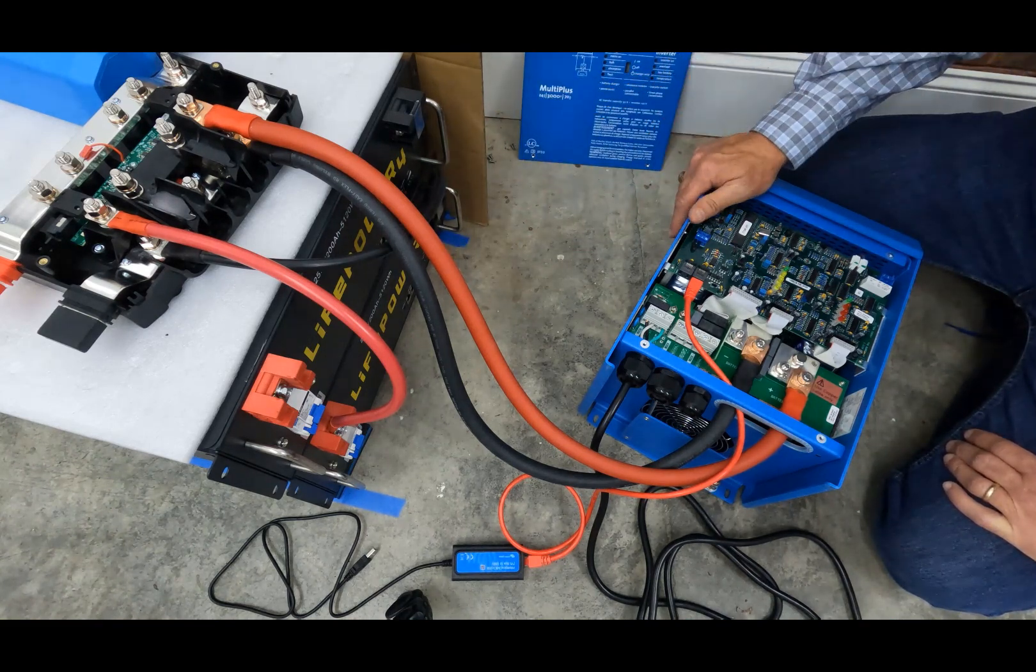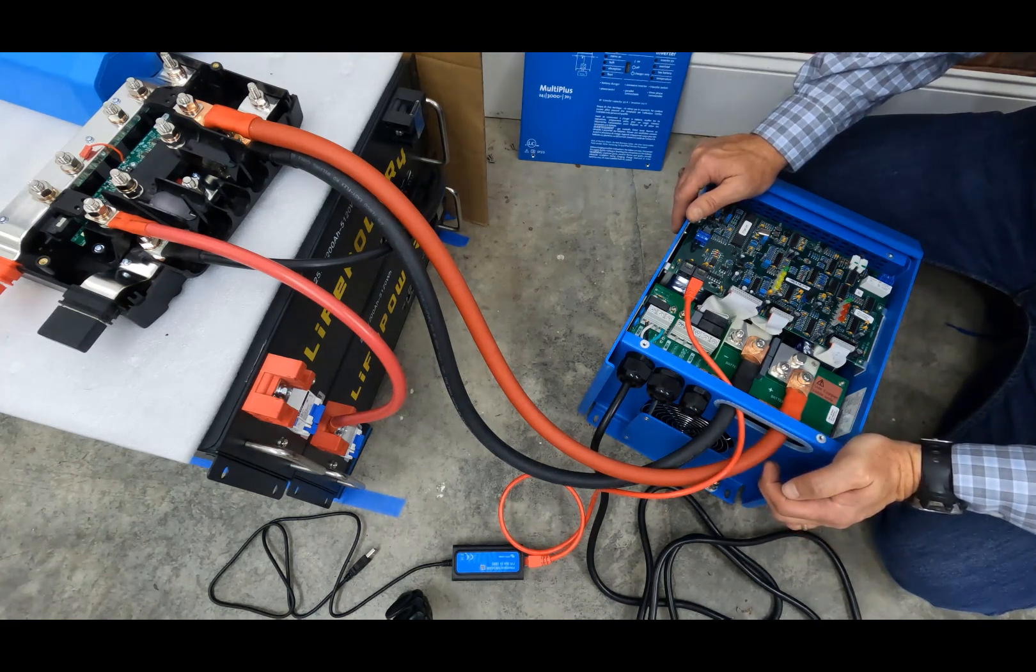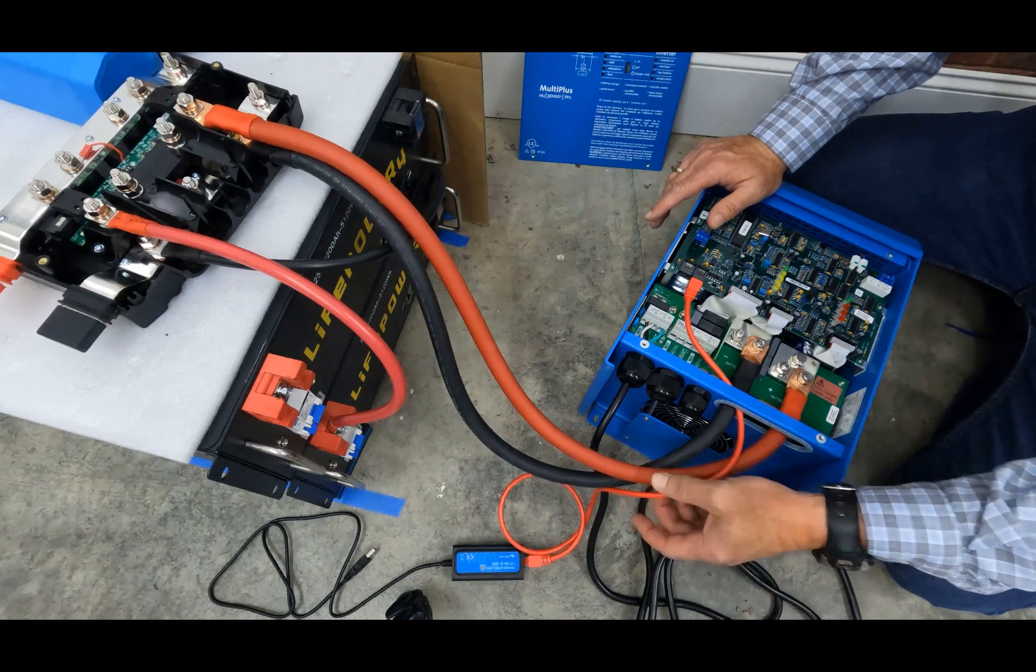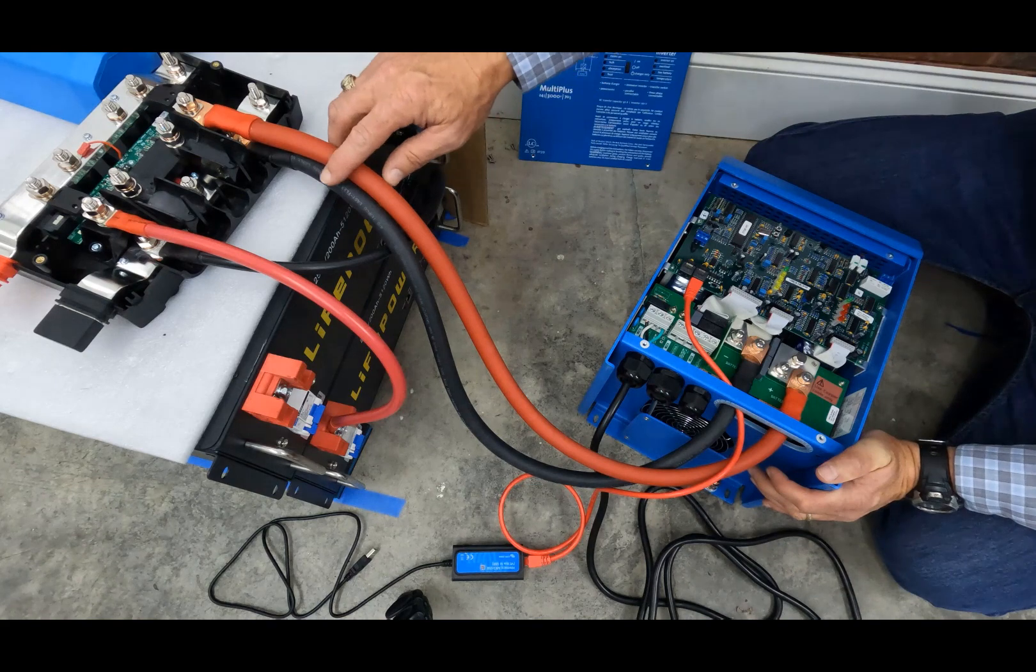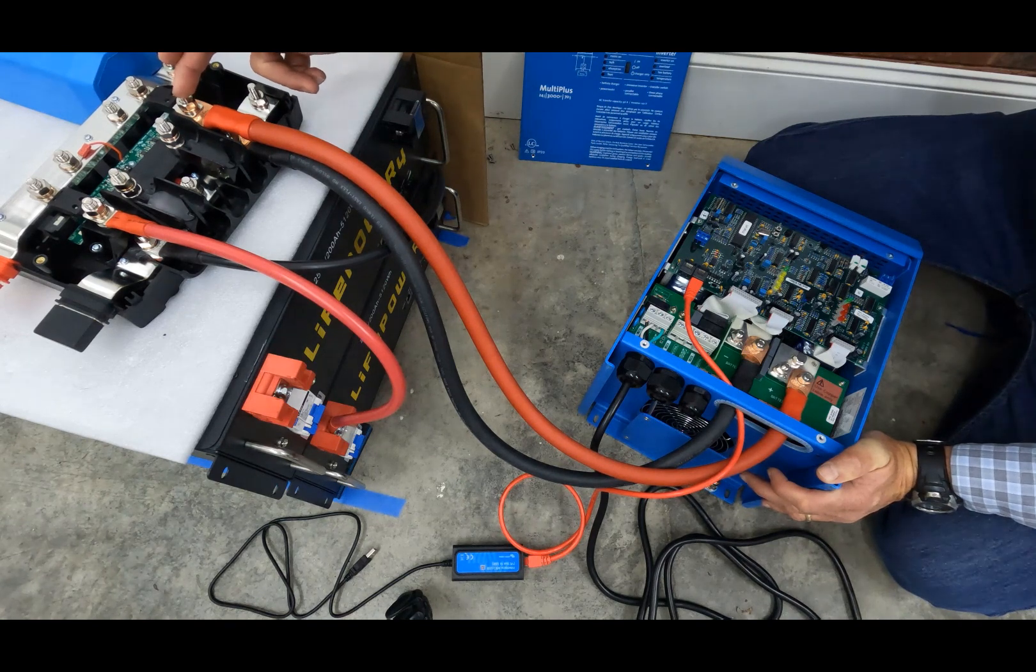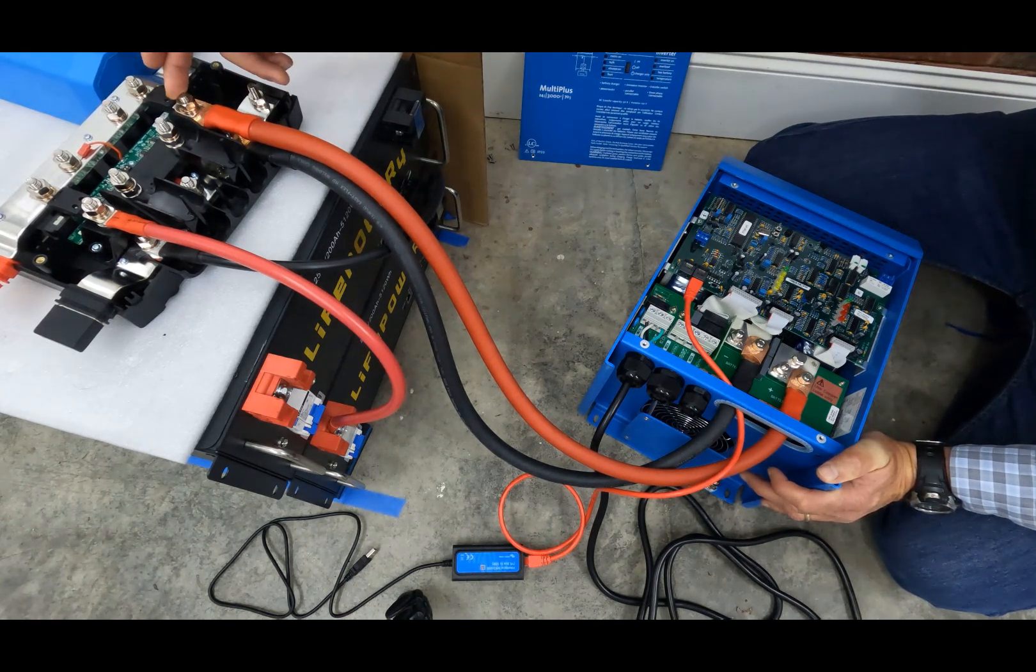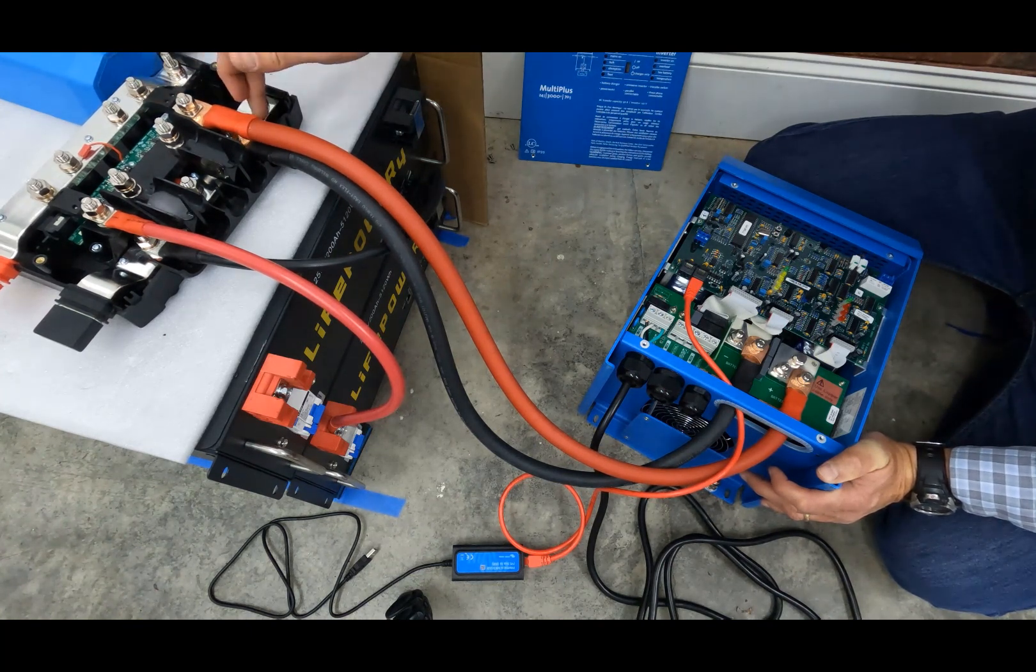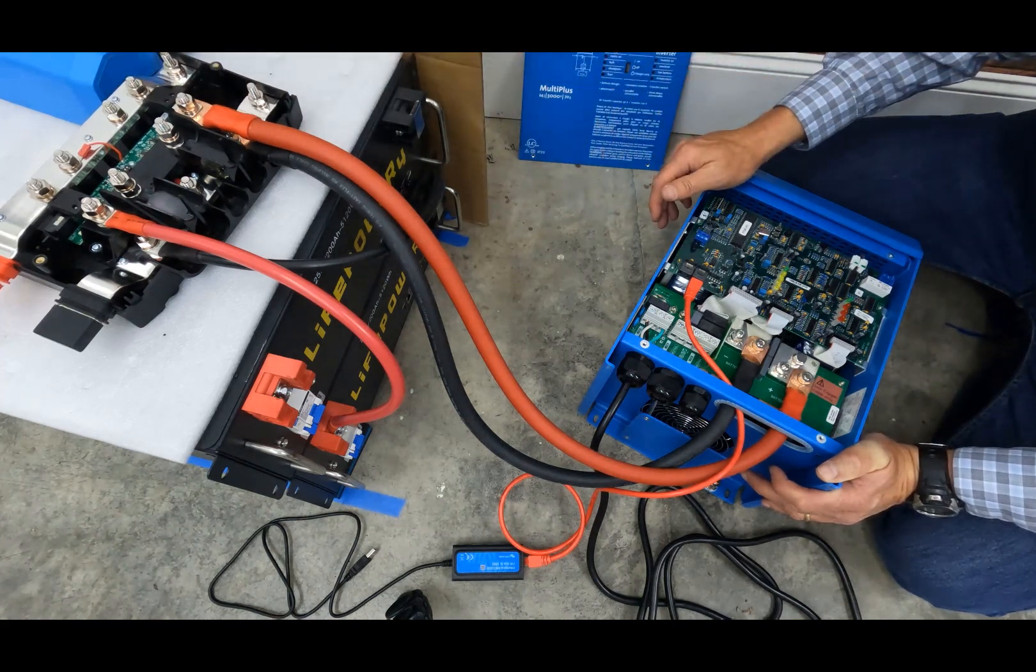What I've done is I've gone through in preparation for the overall design, and I've gone ahead and connected the Victron inverter using four-aught cable back into my Lynx distributor. So it makes it nice and clean in the Lynx distributor to come in, connect the negative on the bottom line, the positive on the top, and then I can put a fuse between this connection and the positive bus bar at the top. So you have a negative bus bar, your positive bus bar, and a fuse in there to make sure everything is working well.